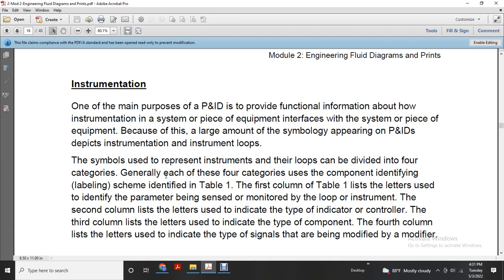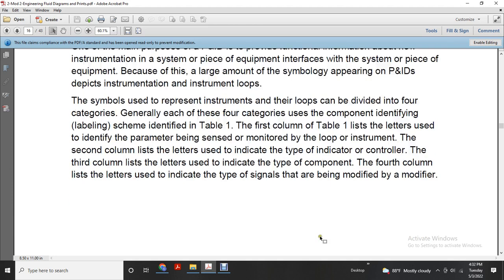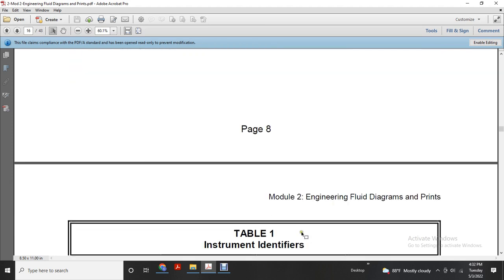The first column of Table 1 lists the letters used to identify the parameter being sensed or monitored by the loop or instrument. The second column lists the letters used to indicate the type of indicator or control. The third column lists the letters used to indicate the type of component. The fourth column lists the letters used to indicate the type of signal that is being modified by a modifier.